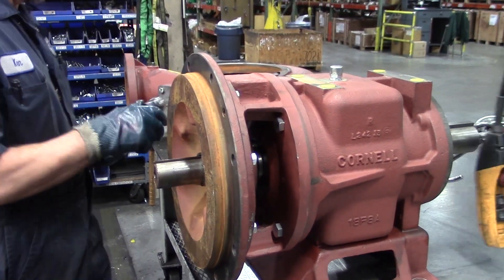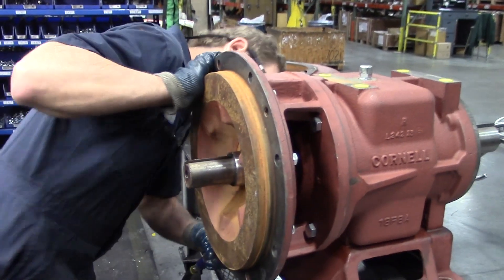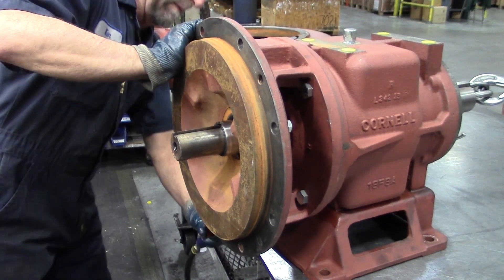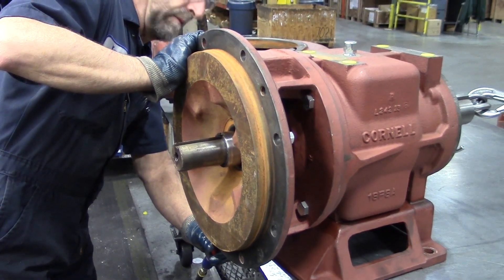One thing you want to do is make sure you save all your impeller shims, so when you put your impeller back on after redoing the seal, you have the proper shimming. Also, when you put the impeller back on, you want to make sure that there's 30 thousandths of back vane clearance.